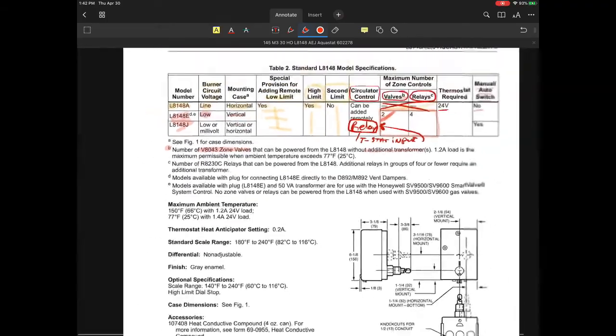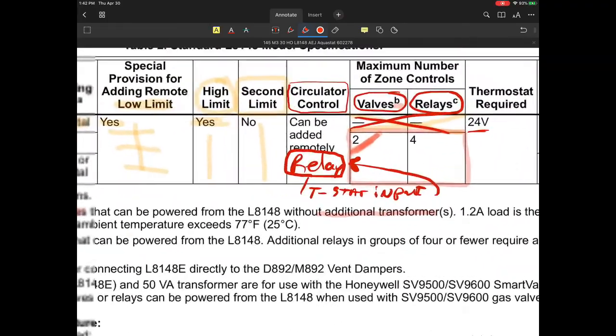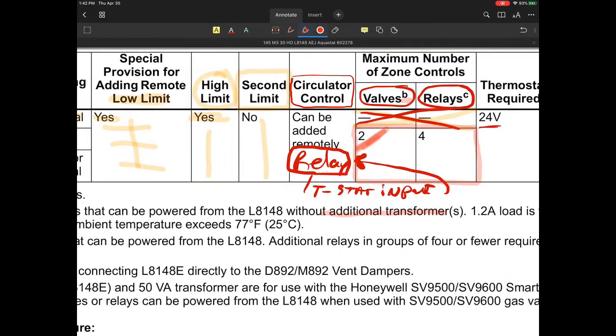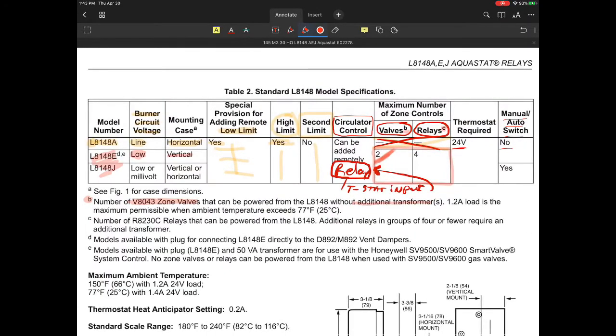In fact, I rarely even like to use the boiler's Aquastat internal transformer power supply to power up zone valves if I can help it. But that is something you have to be aware of, that it will do that. So that's one zone. Like say if I have a relay, they list this as item C.